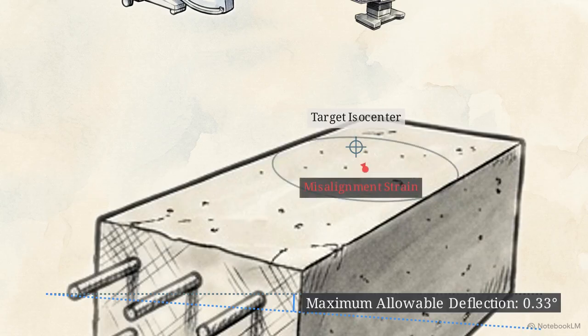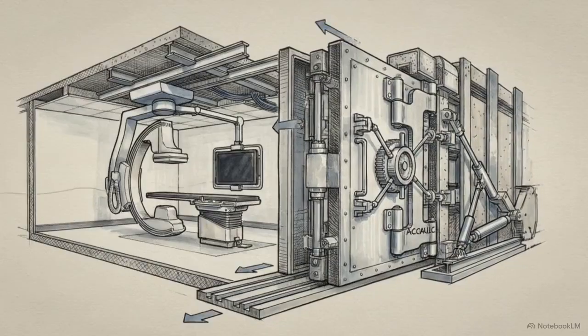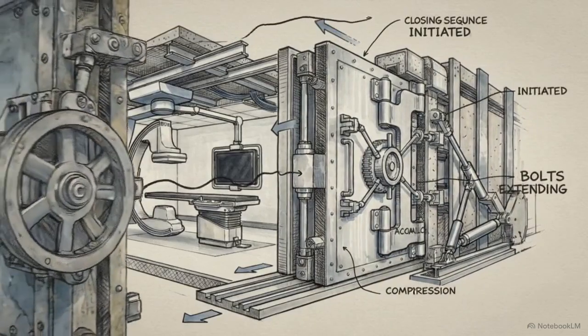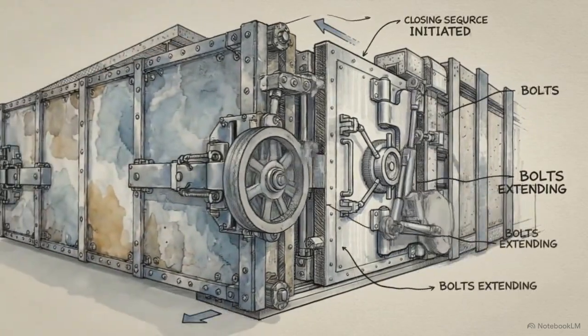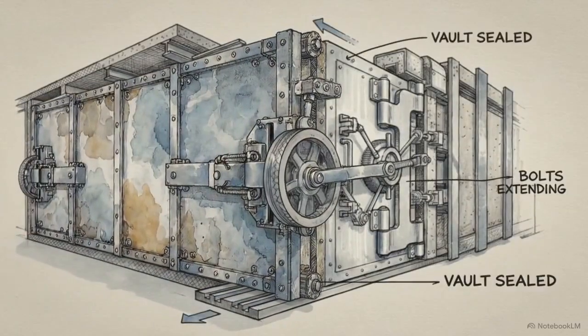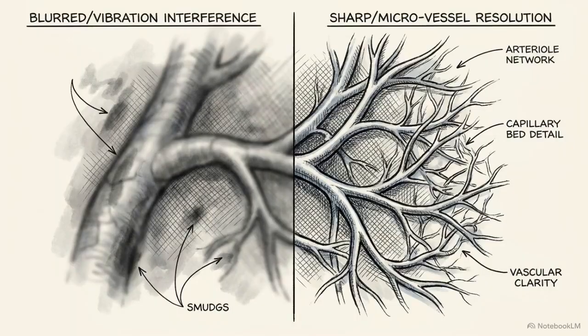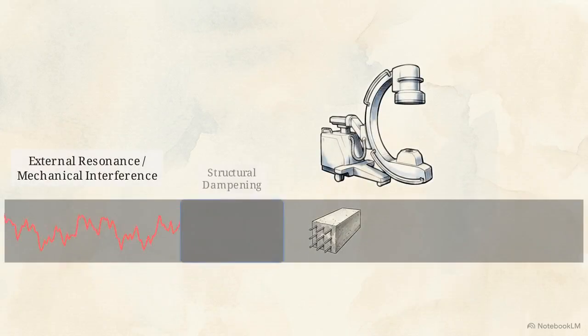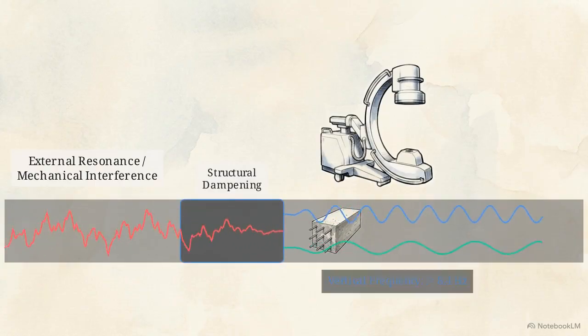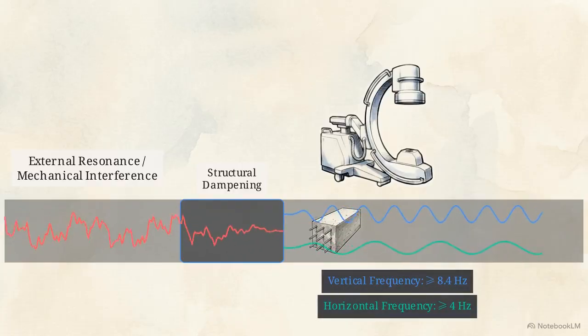As the gantry rotates, even minor deflection causes mechanical strain, forcing the imaging focal point completely out of alignment with the target. The completed room acts as an impenetrable vault, ensuring biological safety for the staff and sub-millimeter geometric accuracy for the imaging hardware. Beyond macroscopic stability, engineers must mitigate microscopic vibrations capable of blurring high-resolution vascular imaging. To block foot traffic resonance and mechanical interference, the floor structure is engineered to meet specific fundamental frequencies, a minimum of 8.4 Hz vertically and 4 Hz horizontally.